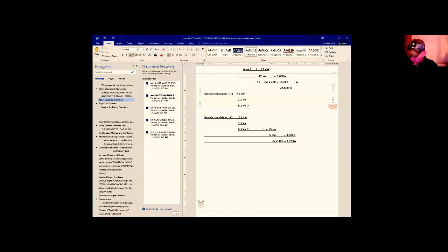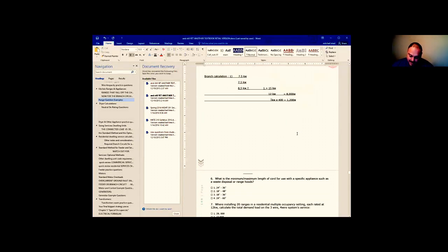So the 24 kW on row 1, the first 12 kW of that is 8,000. And that leaves you with 12 additional steps then. Each one of those is going to be 400 watts. So you got 12 times 4, it's 48, right? And the 4,800 added to the 8,000 base number you got there in column C comes out to 12,800. All right.